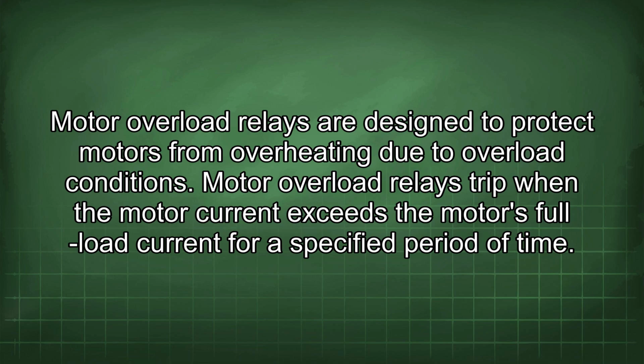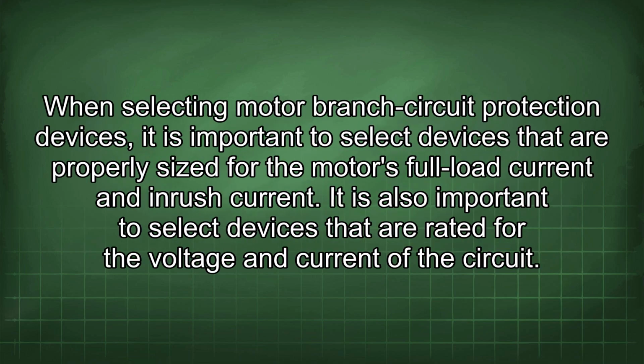Motor overload relays are designed to protect motors from overheating due to overload conditions. Motor overload relays trip when the motor current exceeds the motor's full load current for a specified period of time. When selecting motor branch circuit protection devices, it is important to select devices that are properly sized for the motor's full load current and inrush current. It is also important to select devices that are rated for the voltage and current of the circuit.